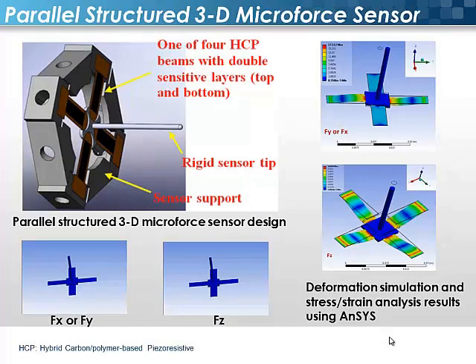Here is the result of the simulation. The structure of our sensor has a standard and a sensor tip. We have 4 sensing films, and each film has a bottom and a top layer with the sensitive materials. By the simulation result, we can find that the deformation and deflection are symmetric when we apply force in the X, Y, or Z direction. This principle is very important when we design a 3D self-decoupling microforce sensor.